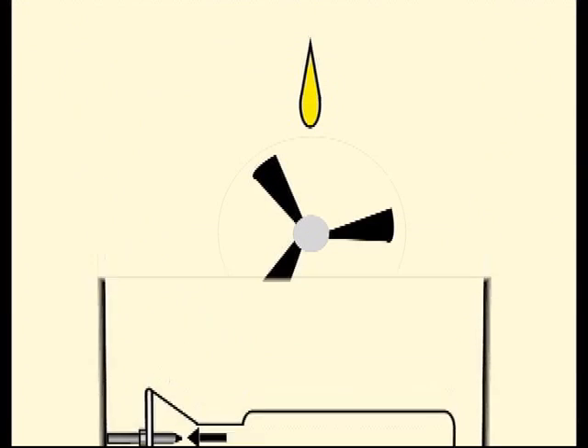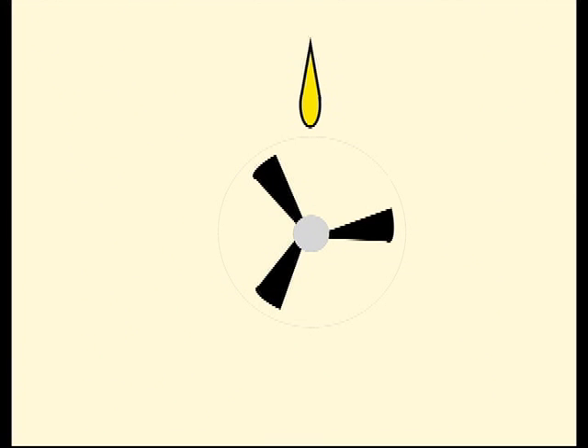The air inlet also has a butterfly valve which can be adjusted. When both are properly adjusted, they yield a blue flame and no smoke.